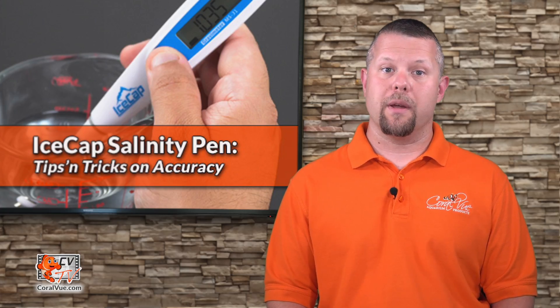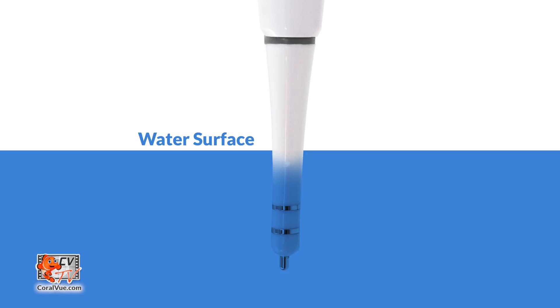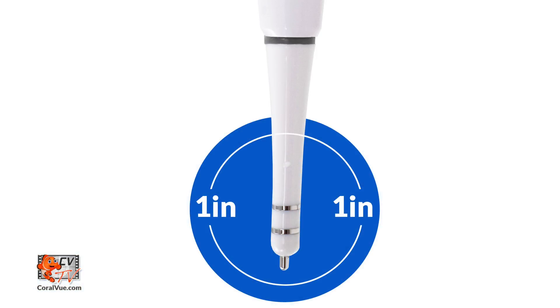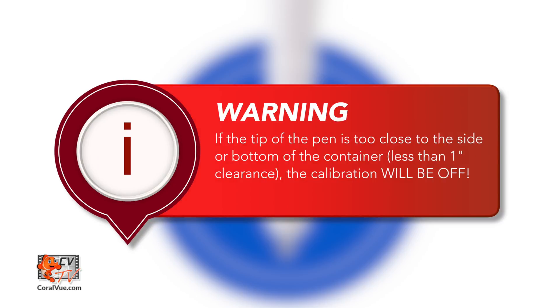When calibrating the pen, be sure to submerge the tip of the pen completely so that the two rings are below the surface. Also, it is very important to ensure that there is a one inch clearance all the way around the tip of the pen. If the tip of the pen is too close to the side or the bottom surface, the calibration will be off.